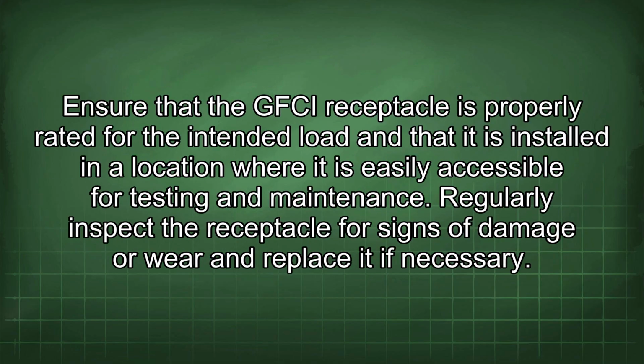Ensure that the GFCI receptacle is properly rated for the intended load and that it is installed in a location where it is easily accessible for testing and maintenance. Regularly inspect the receptacle for signs of damage or wear and replace it if necessary.